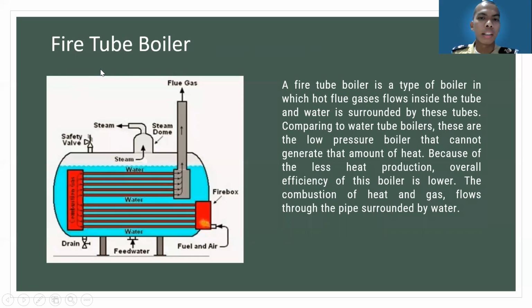And next, I would like to explain about fire tube boilers. A fire tube boiler is a type of boiler in which hot flue gas flows inside the tubes and the water surrounds these tubes. Compared to water tube boilers, these are low pressure boilers that cannot generate that amount of heat. Because of the lower heat production, the overall efficiency of this boiler is lower. The combustion heat and gas flow through the pipes surrounded by the water.